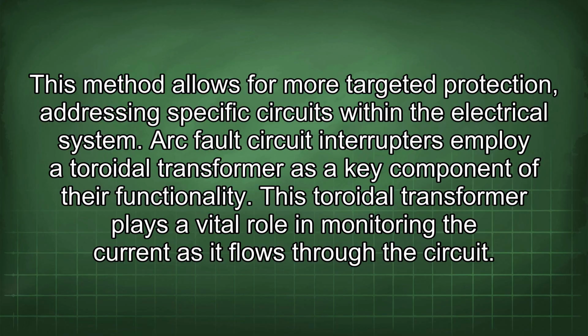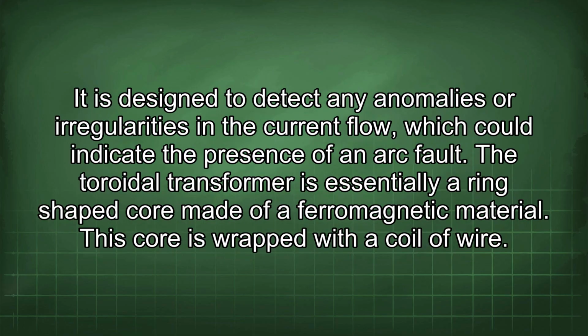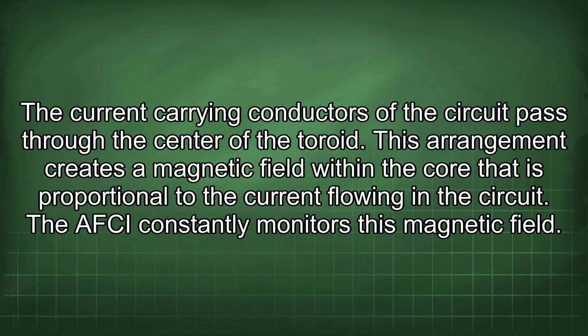Arc fault circuit interrupters employ a toroidal transformer as a key component of their functionality. This toroidal transformer plays a vital role in monitoring the current as it flows through the circuit. It is designed to detect any anomalies or irregularities in the current flow, which could indicate the presence of an arc fault. The toroidal transformer is essentially a ring-shaped core made of a ferromagnetic material. This core is wrapped with a coil of wire. The current-carrying conductors of the circuit pass through the center of the toroid. This arrangement creates a magnetic field within the core that is proportional to the current flowing in the circuit. The AFCI constantly monitors this magnetic field.